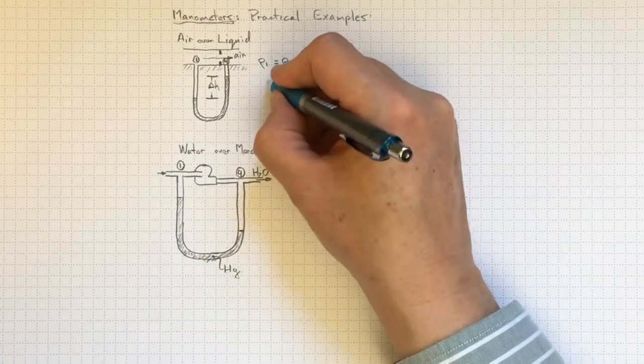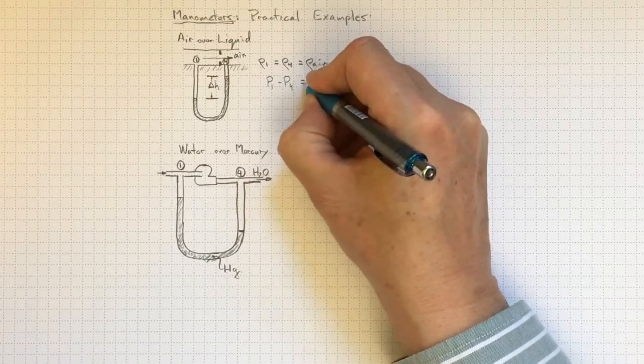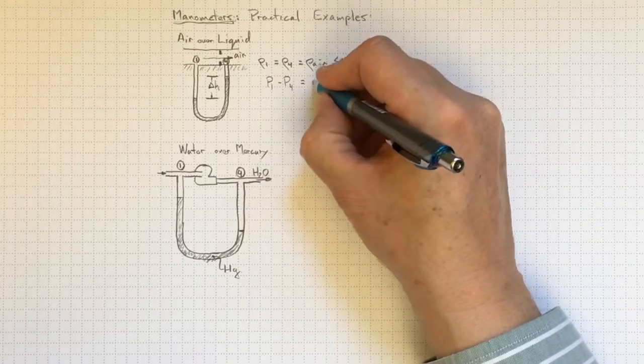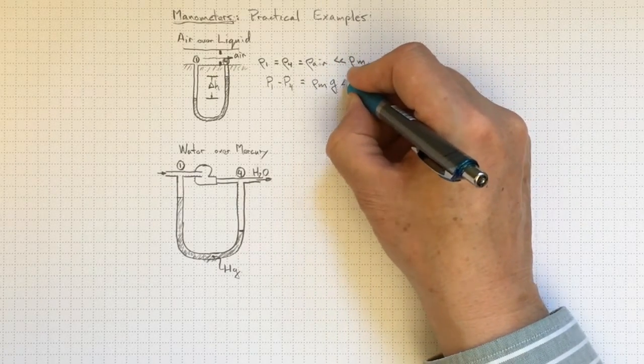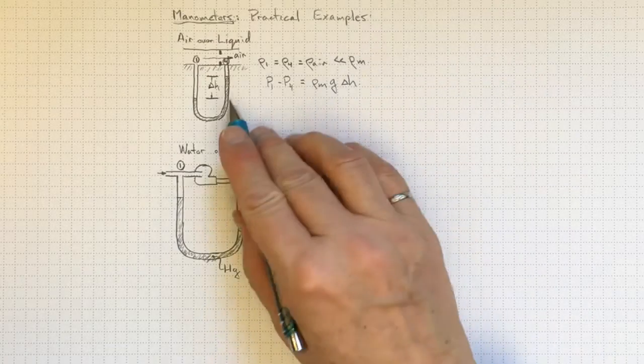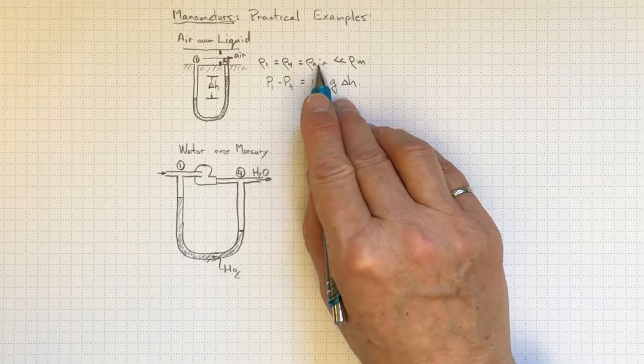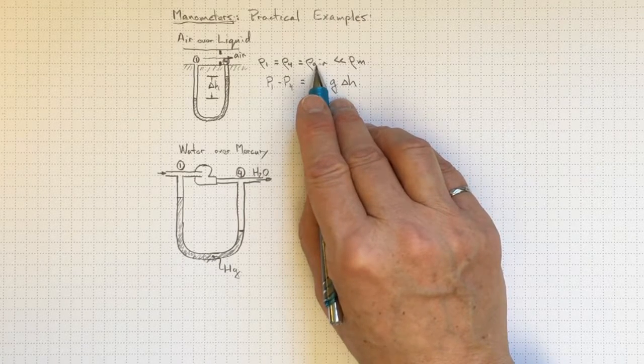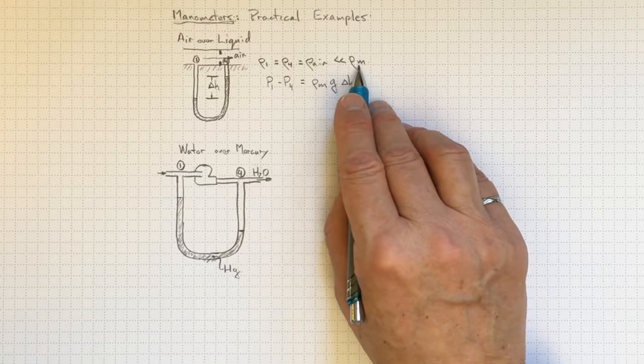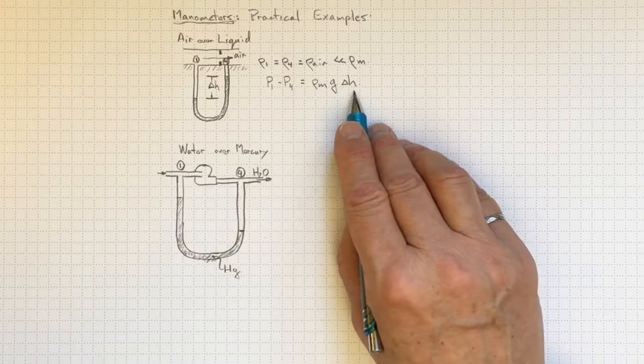And so the pressure at location 1 minus the pressure at location 4 will be equal to rho of the manometer fluid times G times delta H. So this is a really simple application, and it's really simple because we've been able to neglect the density of the air because it's probably about 1,000 times less than the density of the manometer fluid. So we can still get a very accurate measurement of pressure this way.